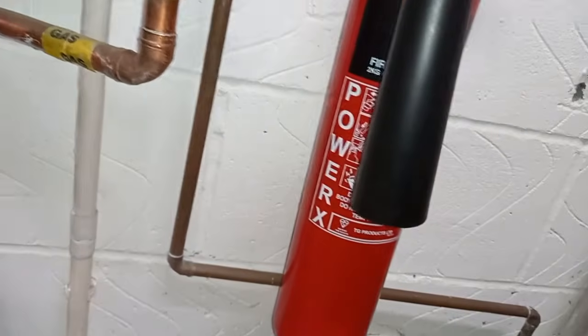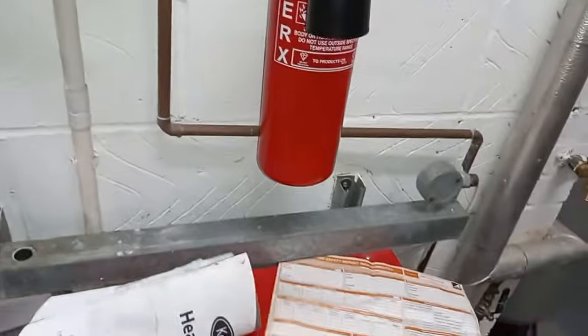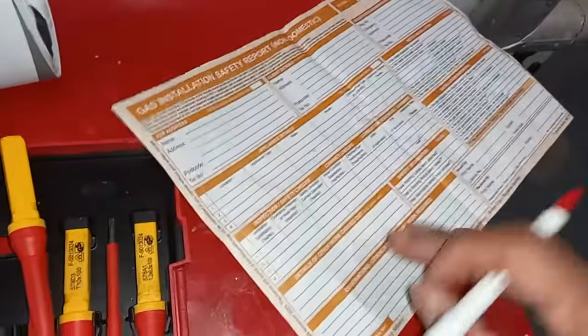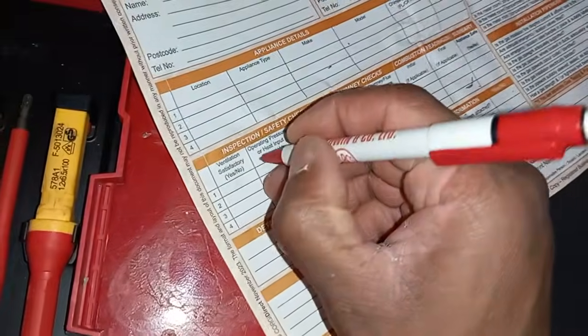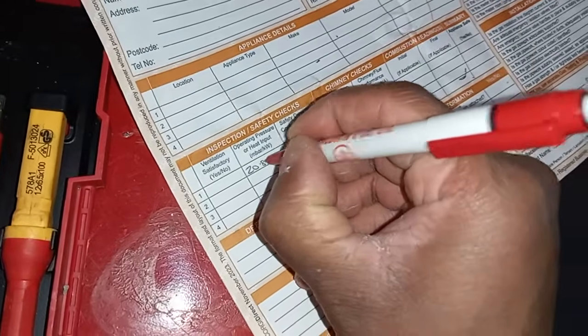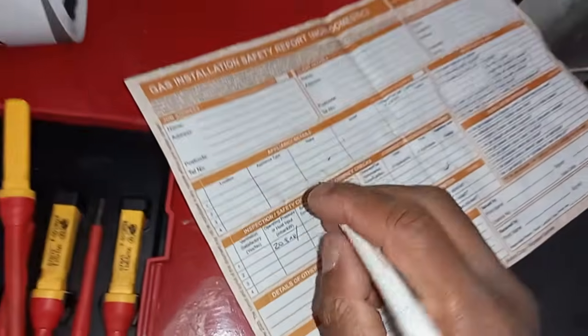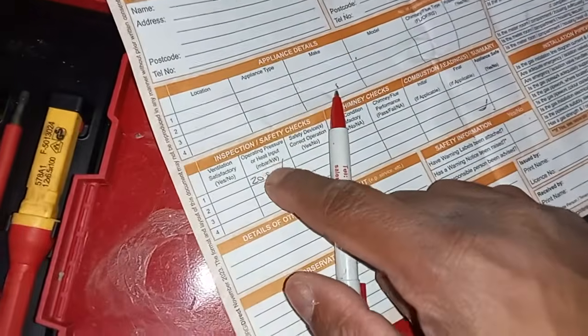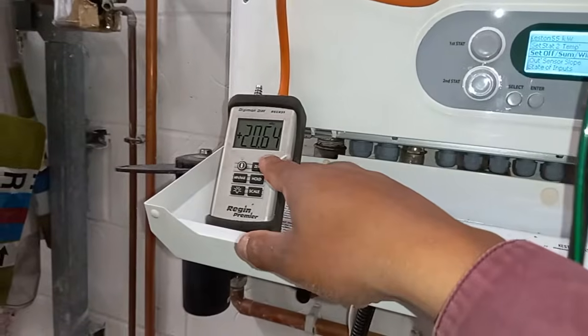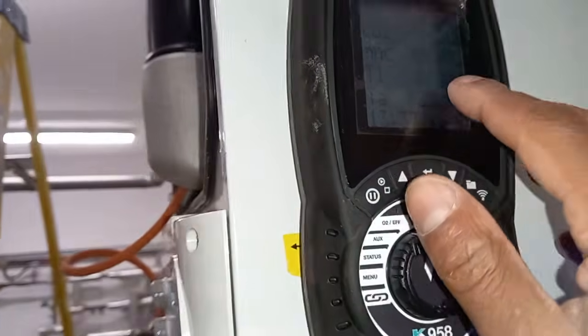I can write it straight down in here in my service book, or my service sheet, my working pressure. So I know I've got 20.8. So even here, I could write 20.8 millibar. I could do the kilowatts later if I want to, but what's this asking me for? It's asking for millibar or kilowatt. Okay, so that's there. Has it stabilized?